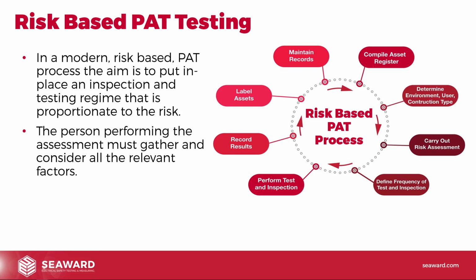But this is a modern risk-based system. So there's no such thing as a fixed inspection and test period. We don't just apply 12 months for everything. We're assessing the risk, inspecting and testing proportionate to that risk, and then we're constantly keeping that under review. That's the important thing. The whole cycle continues because we're constantly reviewing this and making corrections. So if the risk increases, then we change the frequencies to reflect that, and that's built into the process. If the risk decreases, then again we can change the frequencies to cope with that. If any of the factors change, we can build that into the risk assessment, and then we've got the outcome.